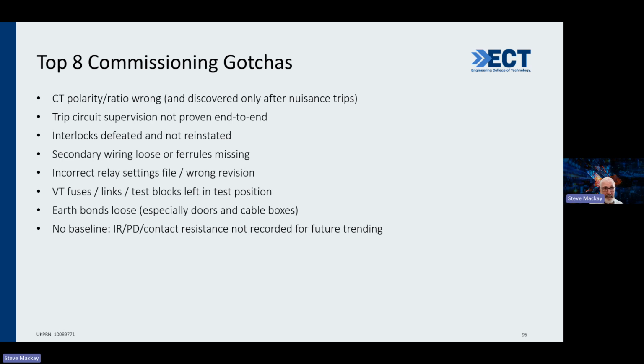In essence, if I can paraphrase two laws I always use when I'm on a site doing commissioning or installation checking. The first one I always use with engineering is: when there's any doubt, there's no doubt. If you've got any doubt whether the CT polarity is right or wrong, you know for sure it's wrong, or if the ratio is wrongly recorded, you know for sure there's an error. That's the first law. The second rule is the KISS principle. If you're testing anything, try to keep it simple. Keep it simple, stupid. Simplicity in everything you do is absolutely critical.